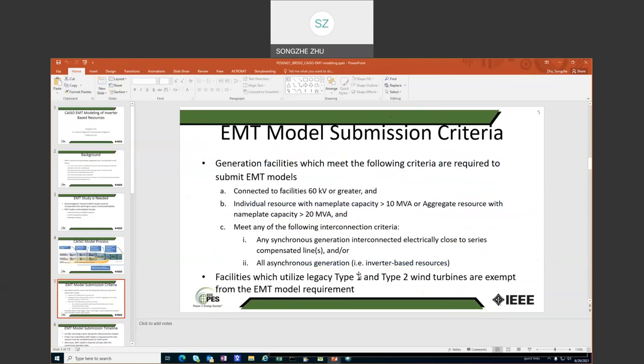Regarding the EMT model submission, we have our criteria for inverter-based resources. EMT models are required if the facility connects at 60 kV or above and has an individual resource capacity greater than 10 MVA or an aggregate resource nameplate greater than 20 MVA. The majority of IBRs would meet this requirement, and they must provide EMT models. Only IBRs in the distribution system lower than 60 kV, which could also be a sub-transmission system, that are small don't need to provide. With that, we are currently trying to collect more than 100 EMT models from those generators.